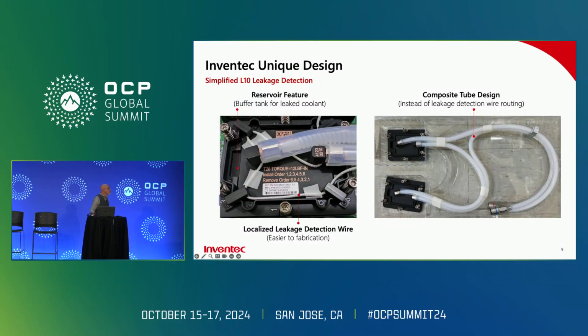Also, when you use liquid cooling, there are some disadvantages sometimes. And a lot of that comes around leakage. So what we have done to address this, we've taken two approaches. We've added a reservoir on a cold plate itself and added liquid detection wires so that we can be alerted when leakage does occur. We also have found that the piping to these are prone to leakage. And so we've developed a very unique method to monitor the pipe leakage level without sensors being wrapped on the wire. And this allows for a more cost-effective solution.